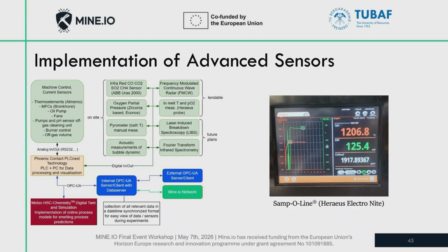We used, for example, the Heraeus Electro Nite probe to detect PO2 inside the slag and the copper, which also gives us a direct temperature measurement. This is not a continuous process, but a dip measurement, a very important one to get the temperature of the melt and the PO2, to drive it safely and to know where we are in the process.